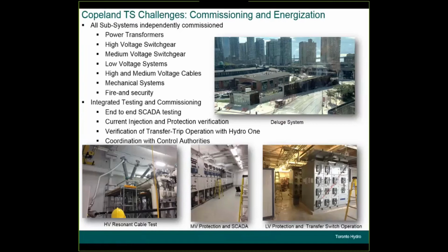So they have a 6-breaker switching system, 230 kV gas-insulated switchgear that affords them the capability to move that open point that we talked about earlier, wherever they may need it, while still providing a radial feed to our 5 pieces of switchgear to feed our 5 future transformers.